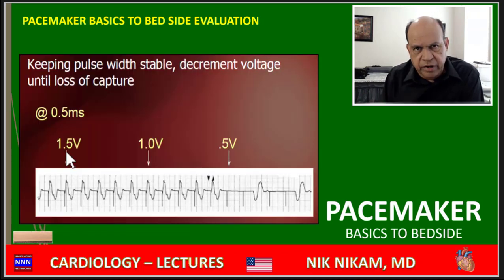When testing the pacemaker for the first time after placing a new lead, we try to pace the ventricles at about 1.5 volts. It's pacing 100%. Then you go to 1.0 - maybe we don't need 1.5, let's go to 1.0. It's pacing. One is doing pretty good.